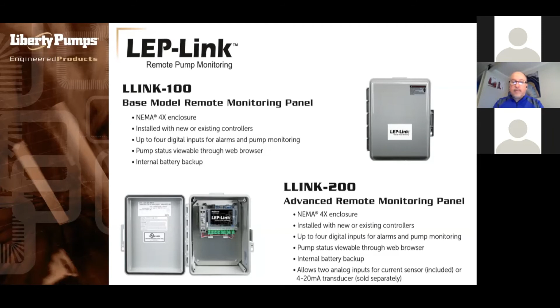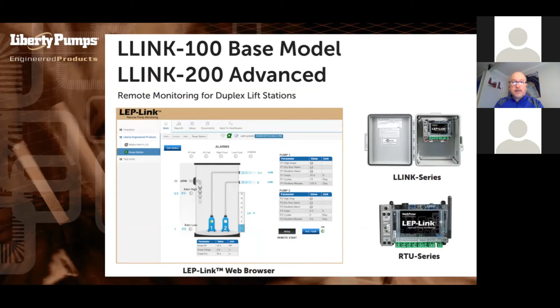So high water levels. This 200 series version actually comes with the current sensor. So it's a little sensor that is wrapped around one of the leads, and it's measuring the current. So that's nice, you can set high amp draws or low amp draws that would send you notifications and gives you some idea of what may be going on with the pump. And then also separately, you can purchase a transducer that can be wired into it. So with that transducer, you can put in parameters as far as diameter and depth of the wet well, and then it's able to measure incoming flow rates and also the flow rates that the pump is pumping. So you can get lots of trending type analysis and graphs of what that pump is doing. And here's a shot of the website, the web browser, and what it would look like. We could do a whole training session just on this.